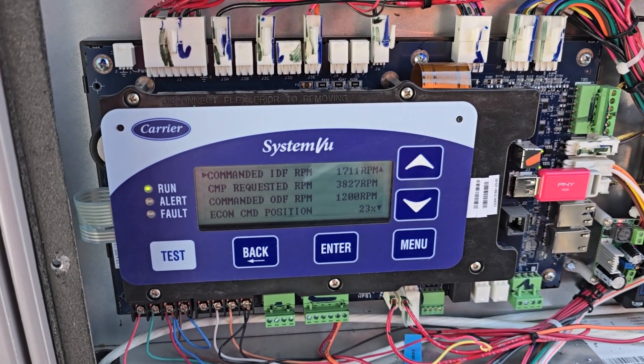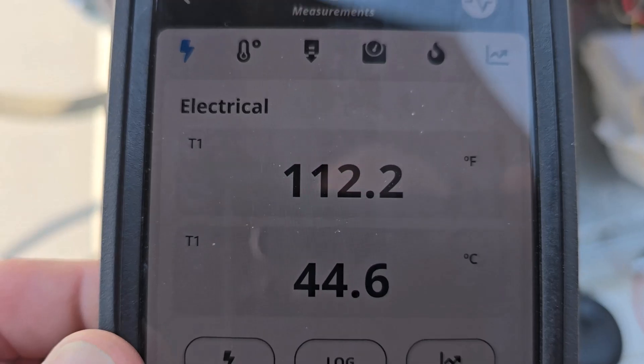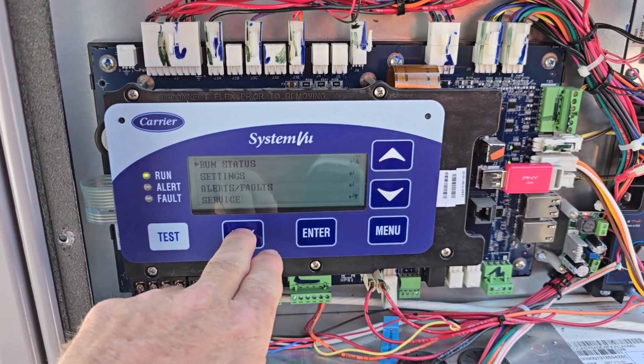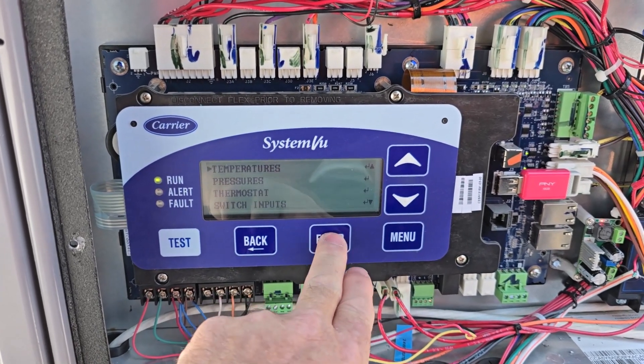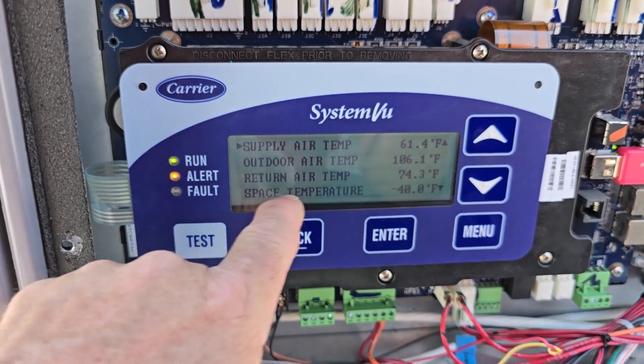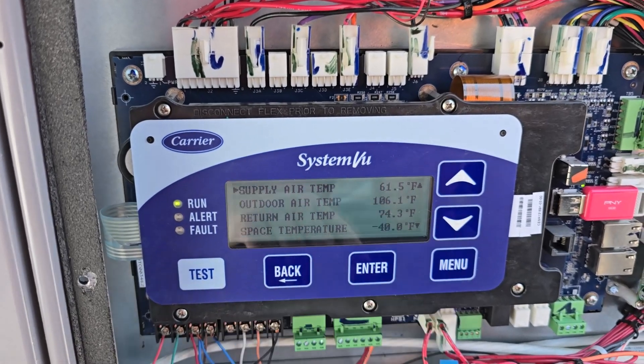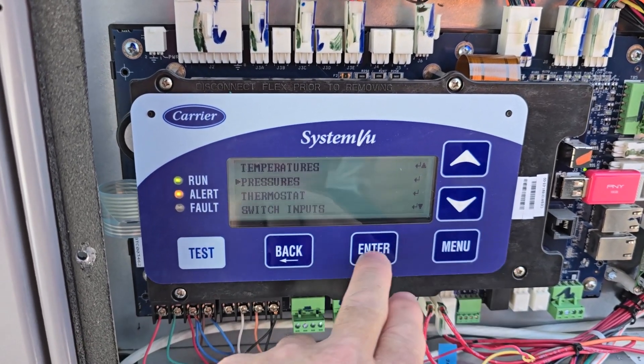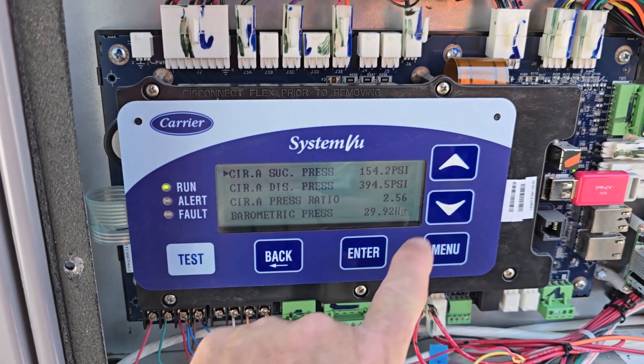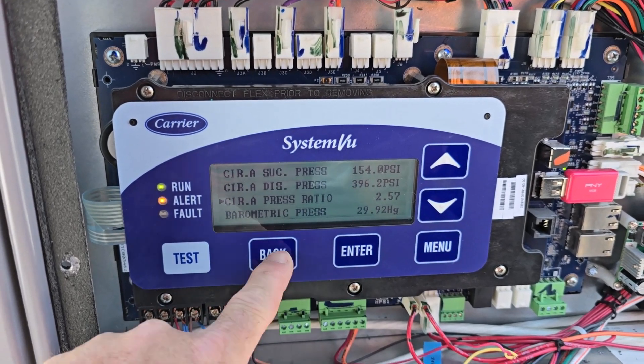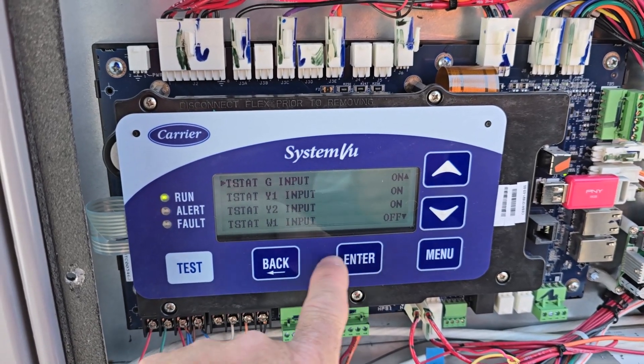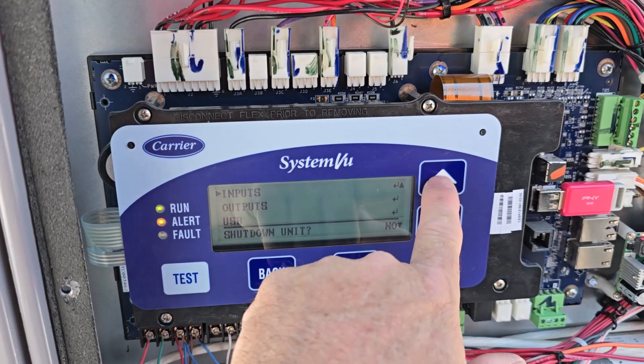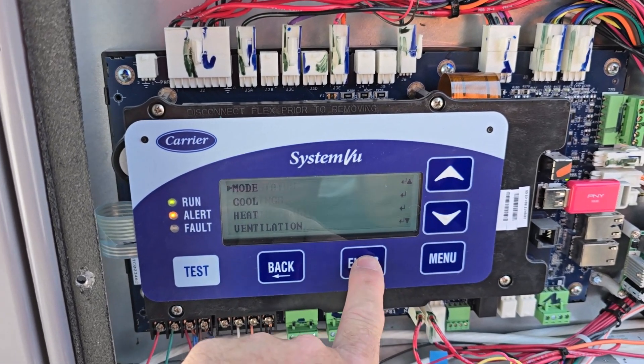3800 RPM. The compressor seems happy. Inverter temp, thermal couple on there. So it's like 112 now. That's doing good. And we go down to the inputs. Temperature 61 degree supply and 74 return. Was running 55 earlier in test mode. So this is just doing what it's doing. 394 discharge, 154 suction. So it's probably going to ramp up a little bit more. 2.6 compression ratio. And you can see the thermostat input. G, Y1, Y2 are all on.